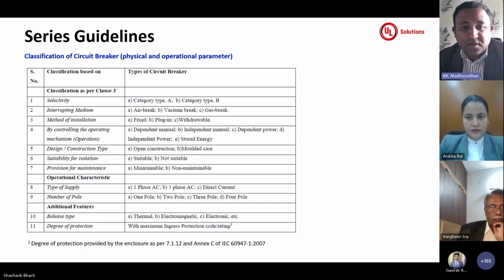Then method of installation: fixed type, plug-in type, or withdrawal type. And also based on the operating mechanism, whether it is an independent manual, a dependent power, or a motor operated. And also based on the design and construction type, whether it is an open type or a closed type, which is nothing but a molded type. And also for suitability of isolation, whether it is suitable for isolation or not. And on the maintenance part, whether it is maintainable or not maintainable. And also based on nature of supply, whether it is single phase, 3-phase, or a DC type application. And based on number of poles, whether it is a single pole to 4 pole, the variants.